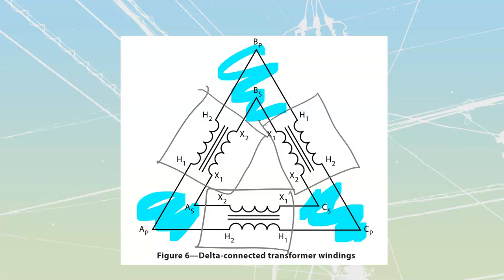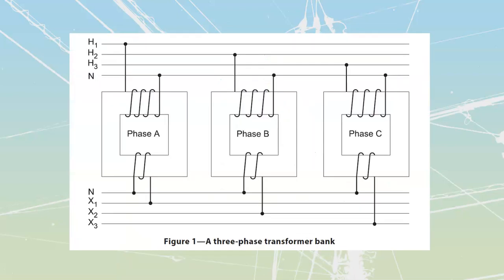There are some advantages to using single-phase transformers connected in a bank. The big advantage is that I'm still able to operate even if I lose one of my transformers, at a reduced output or reduced kVA in some cases. So if you blow a transformer winding, you might be able to continue some processes, you just have to tell your customers to lighten up and wait until you get another one in there.